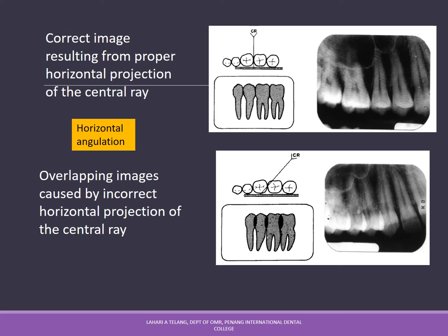Regarding horizontal angulation: with correct horizontal projection of the central ray, where the central x-ray passes at 90 degrees to the film and the embrasures between the teeth, you get very good proximal contacts and correct horizontal angulation. If there is a change in horizontal angulation, overlapping images result — the proximal surfaces of the teeth overlap each other, obscuring findings in that area.